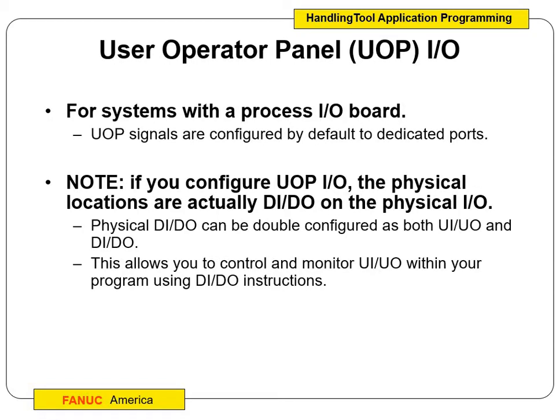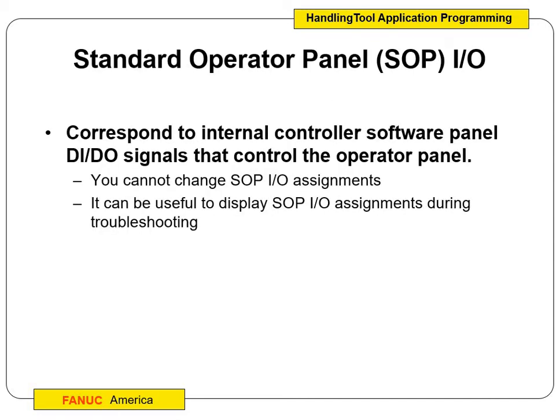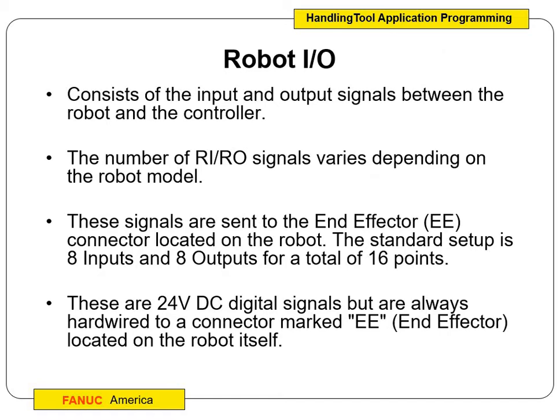Still with the user operator panel — they're configured by default to dedicated ports. If you configure the user operator panel I/O, the physical locations are actually the digital inputs on the physical input and output. So when you open up the panel and look at the card, they are literally the ones right there. Standard operator panel: you cannot change the I/O assignments — they are what they are. On the user one, you can change it around, but this one's kind of defaults and built in. This is what you get and this is what you have to wire up to if you choose to.